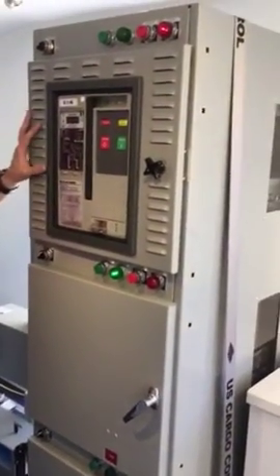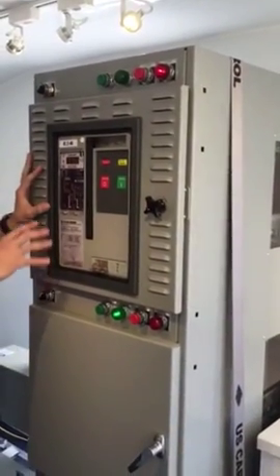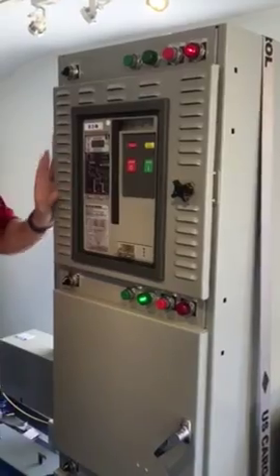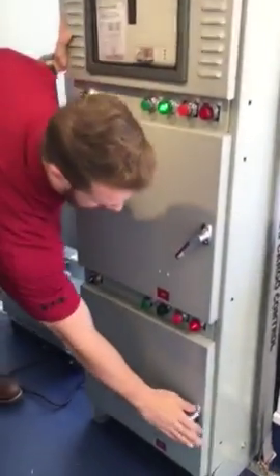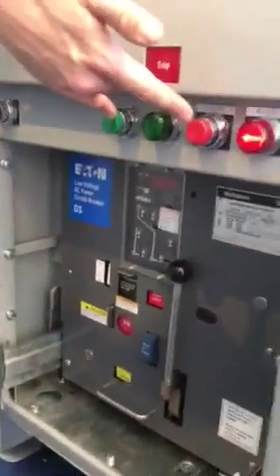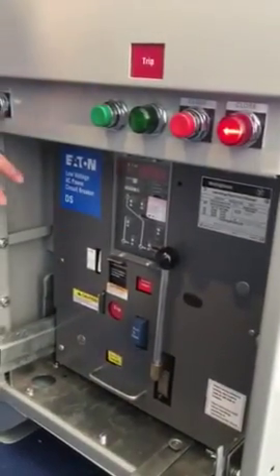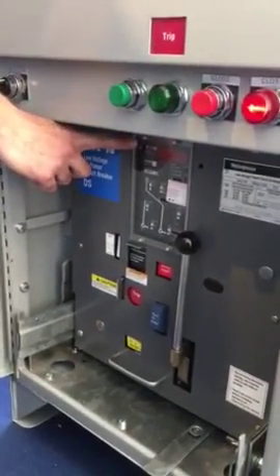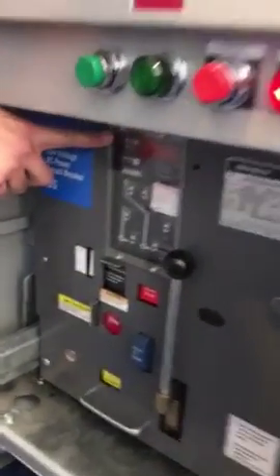So our first demonstration here inside the truck, we have a Westinghouse DS switchgear lineup. The original Westinghouse breaker is down here at the bottom. It is electrically operable here from within the truck. This is the original breaker. It's got an upgraded trip unit on it for communication and arc flash safety protective features.